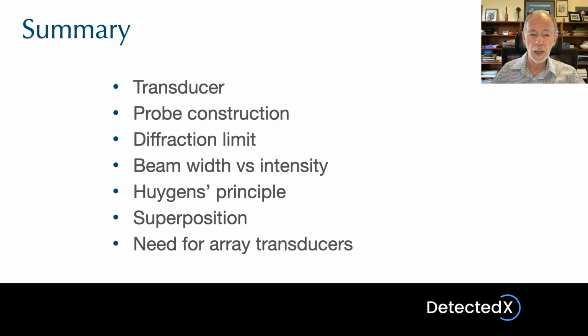I then talked about a couple of things that relate to how the machine does the focusing. First, the variation of intensity with beam width, and the fact that if we maximize the intensity at a particular depth, that's going to guarantee the beam width is minimized at that depth, and that's what we mean when we say focus. Talked about the Huygens principle and the principle of superposition, and the fact that these lead us to the need to cut up the transducer into many small parts, which we refer to as an array transducer. So that's going to lead us into a discussion in the next talk of just how the machine actually focuses for both transmitting and receiving.